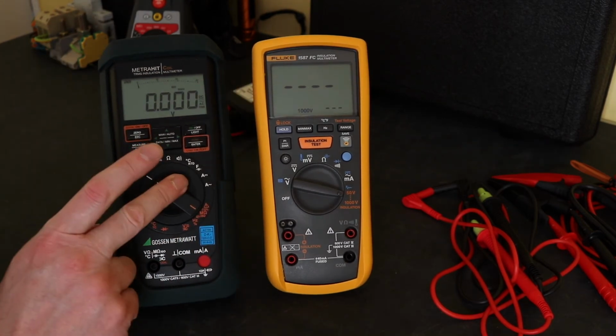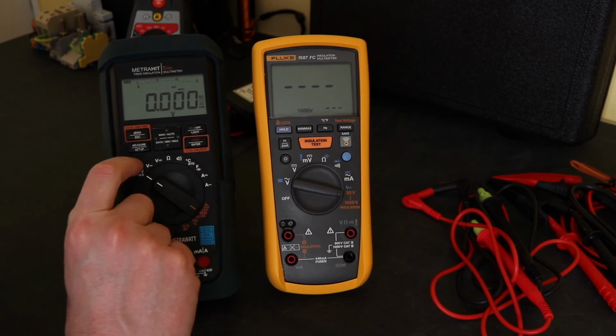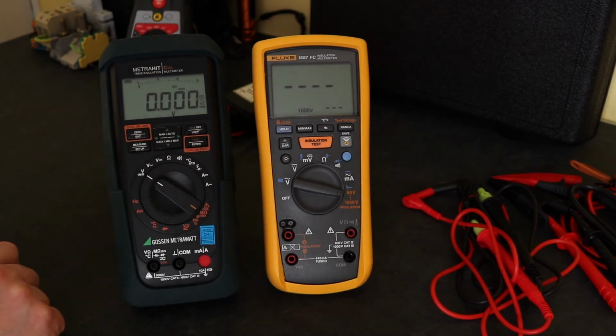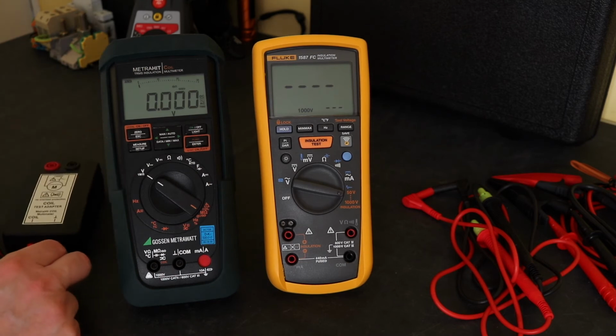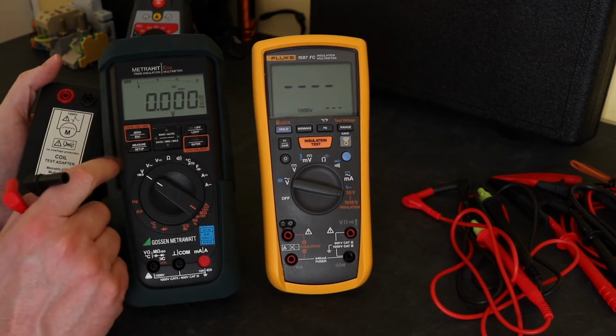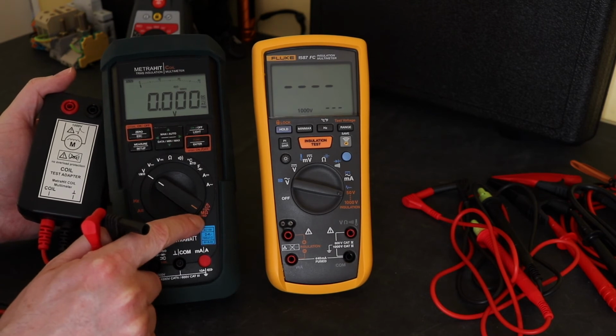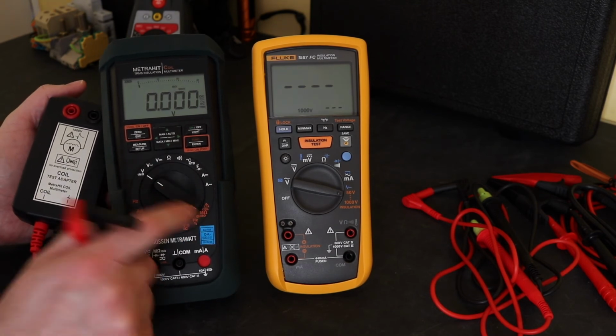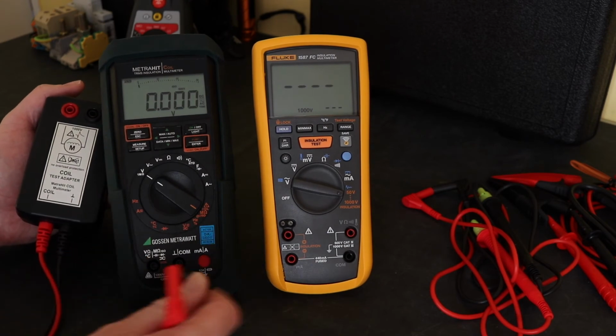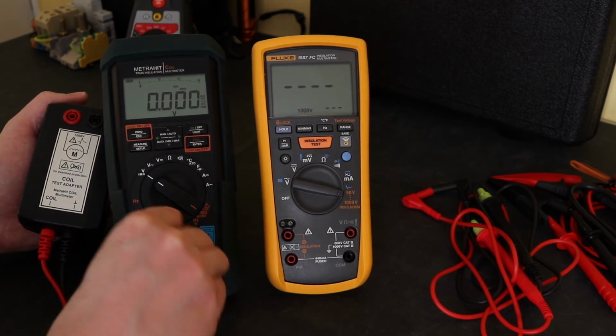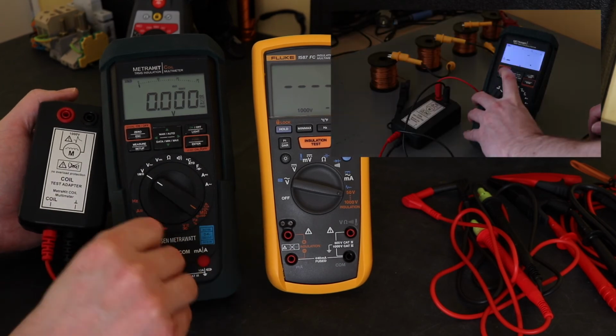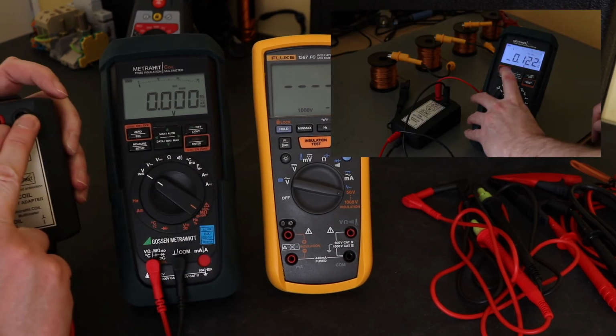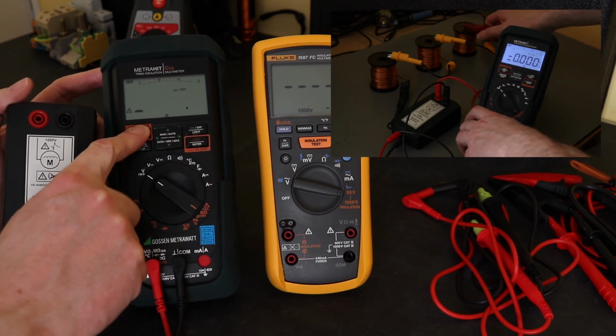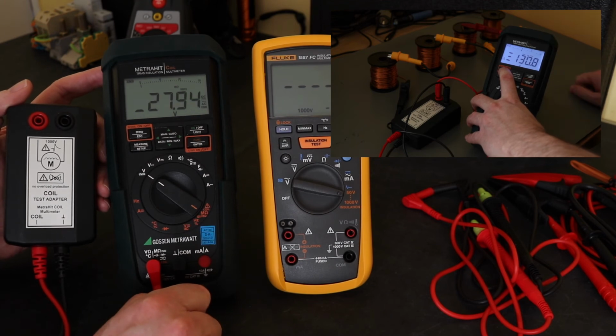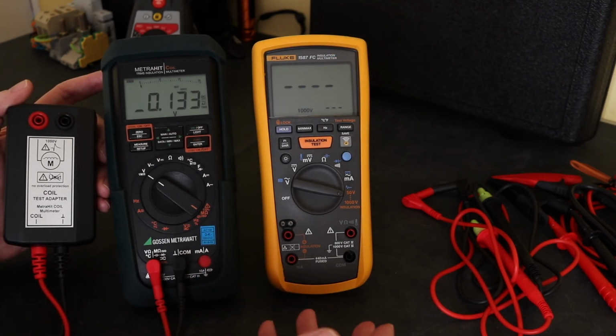Now, what is unique to this instrument that this little fellow does not have is this coil interturn fault tester. And you use this on the insulation test function, except you use the function switch to switch to the coil test, which is actually this one on the insulation test, and it plugs in. I've got some of the videos that show this being used, and then you plug standard leads into here and connect them onto your motor, and then you can test away. And it gives you the reading again, and again you see it flicks back to voltage and discharges.